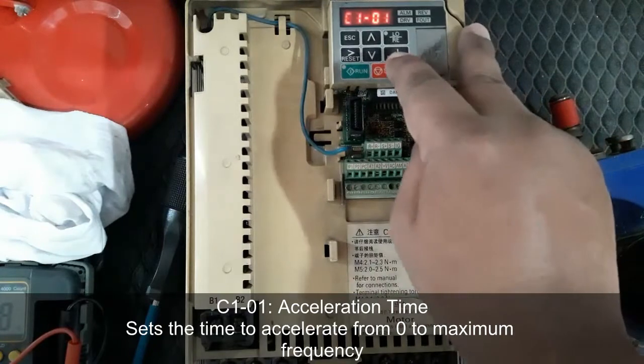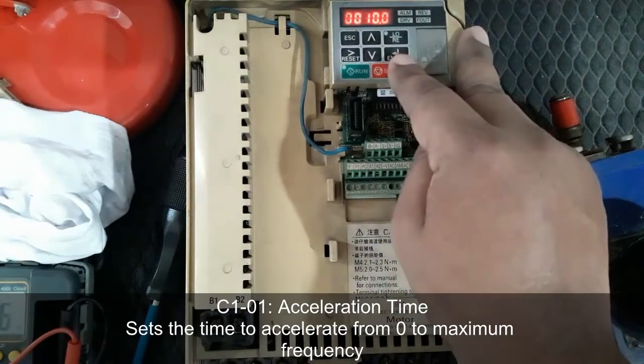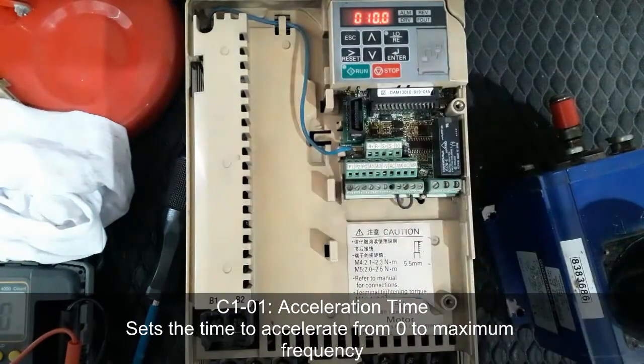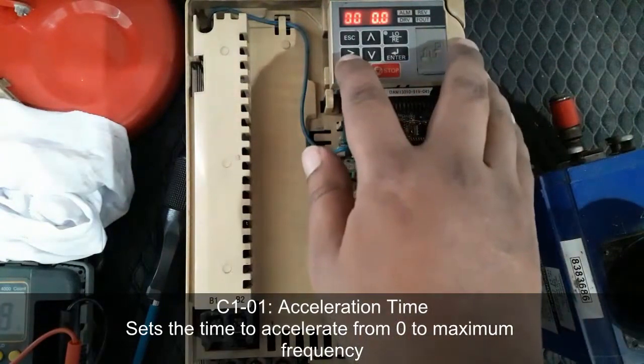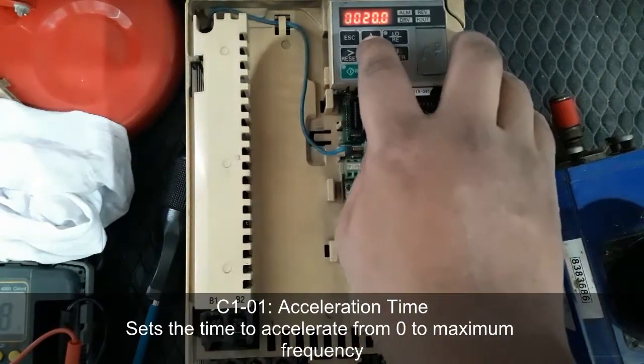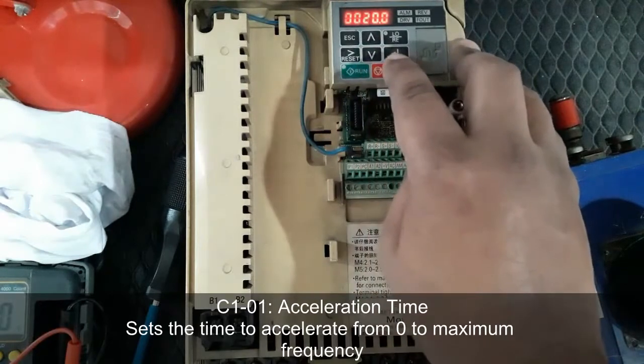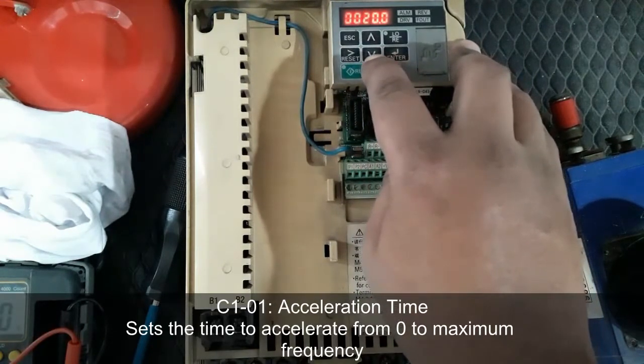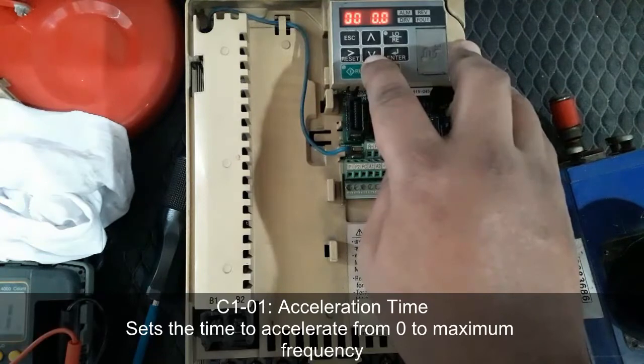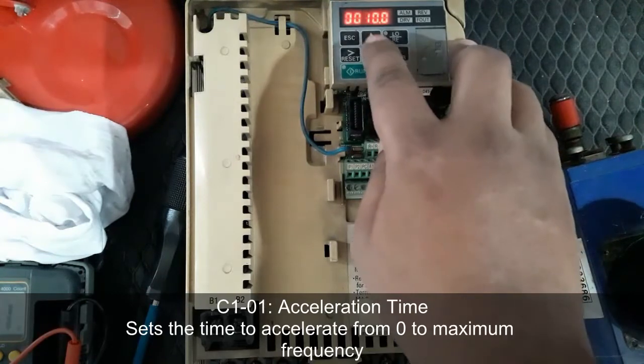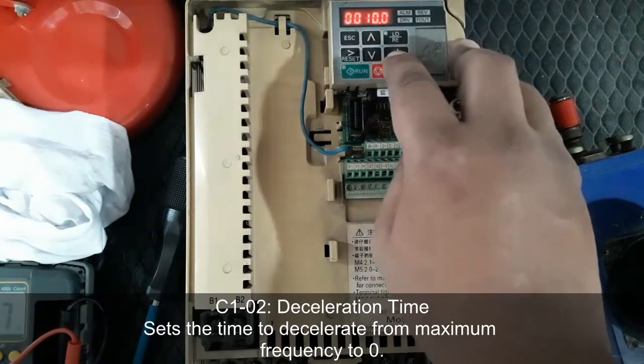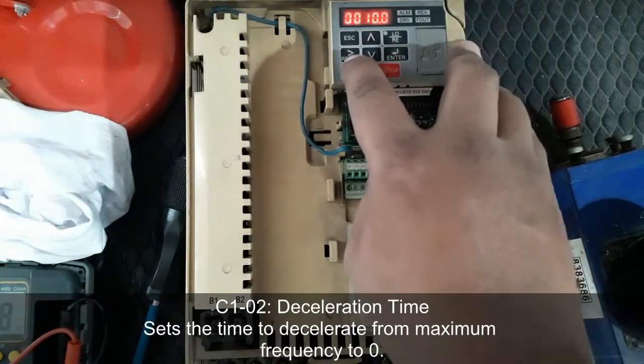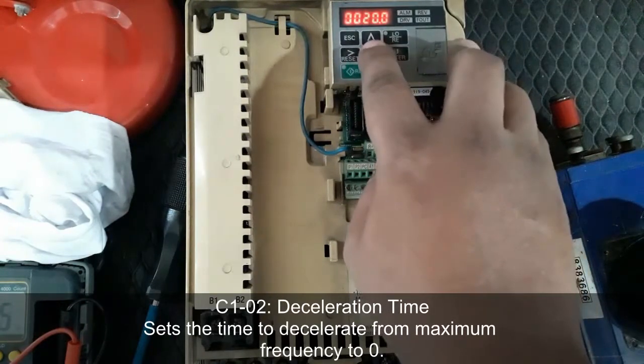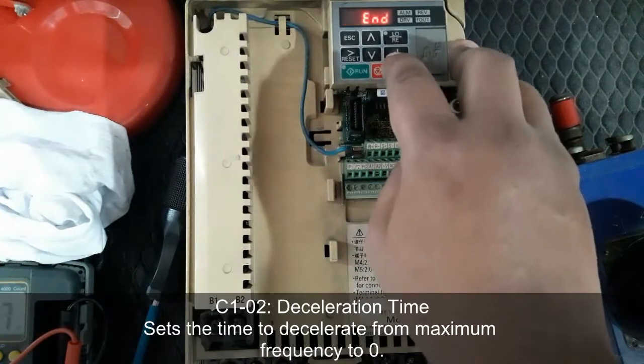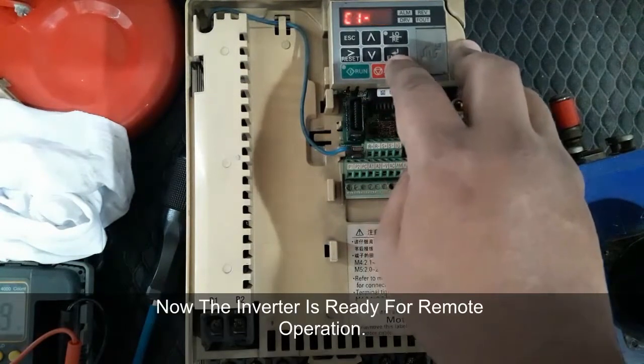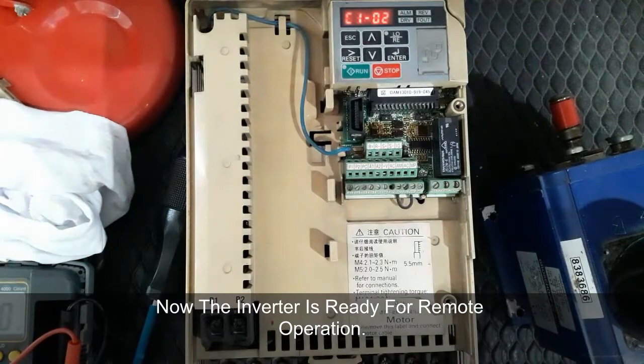Now the acceleration time needs to be set in C101. Acceleration time means the time set to accelerate from 0 to maximum frequency. We set 20 or 10 here, as per your requirement or your machine requirement you can set it, and C102 for deceleration time, which means the time set to decelerate from maximum frequency to 0. Here we set it to 20. So now the inverter is ready for remote operation.